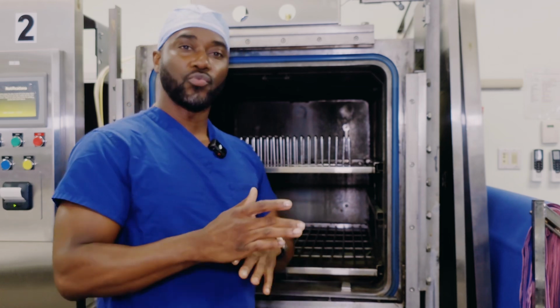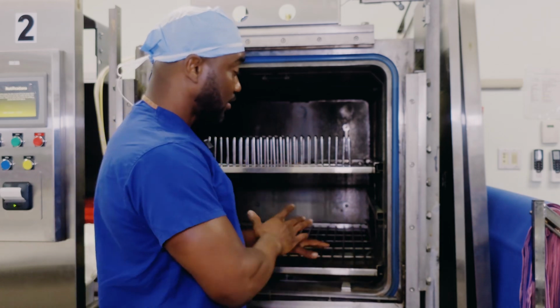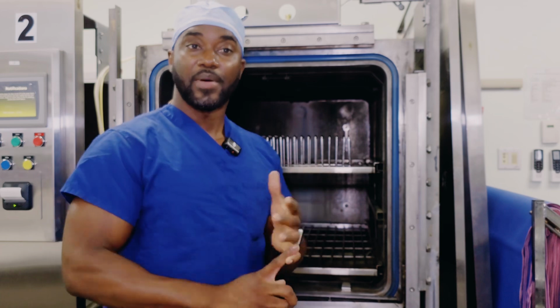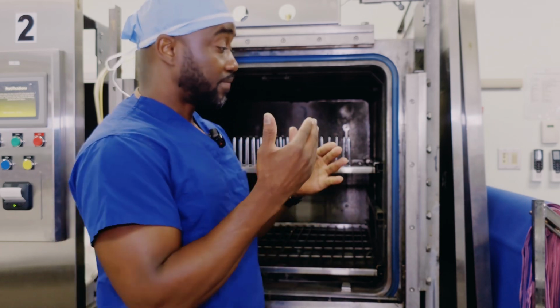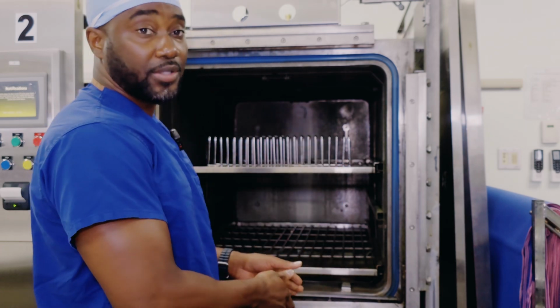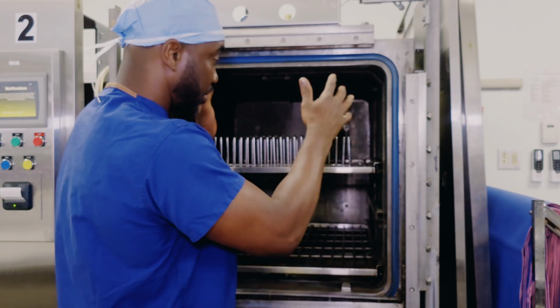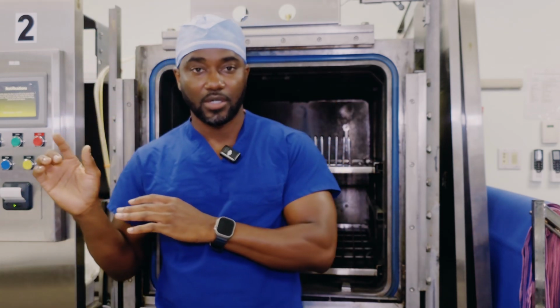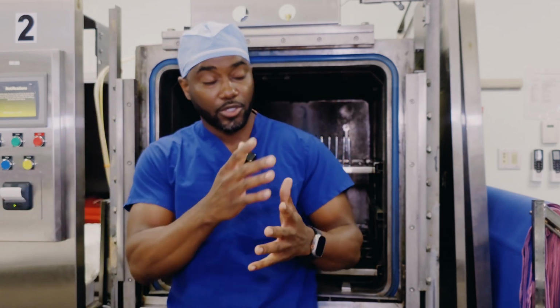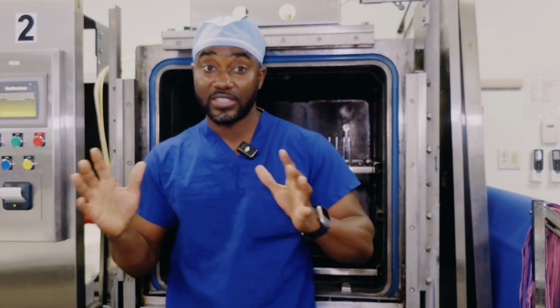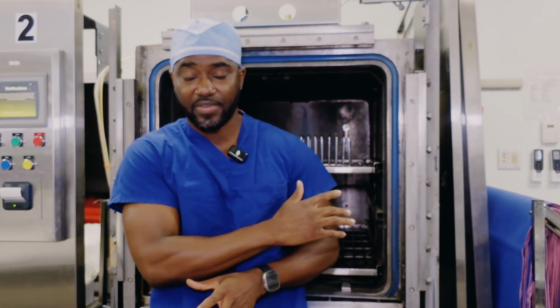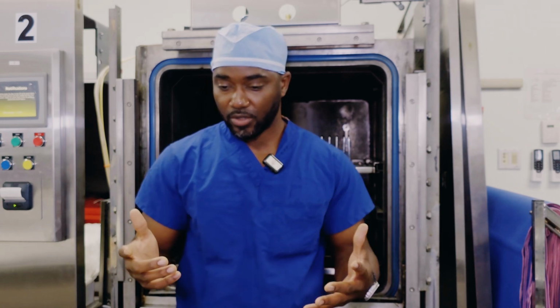And that might lead to wet packs as well. So that's the culprit sometimes, or it might be some piping issue, or the problem might be way down in the boiler system built into this pre-vacuum sterilizer. That is your quality assurance test for your autoclave before any load for the day starts to run on your pre-vacuum autoclave. Usually, it is recommended to run a biological test pack on your first load of the day.